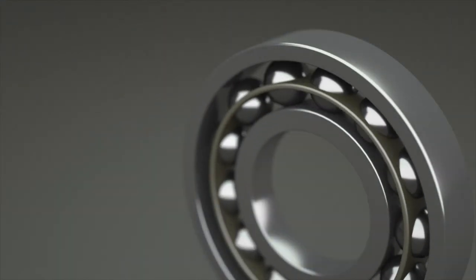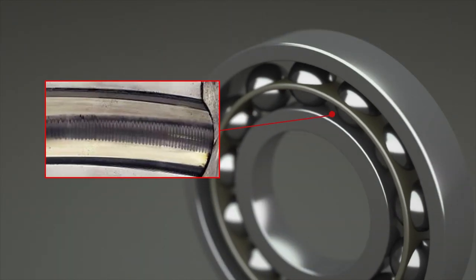If a bearing is experiencing fluting, the inner ring will likely have washboard-like ridges where the electrical current is wearing it down.